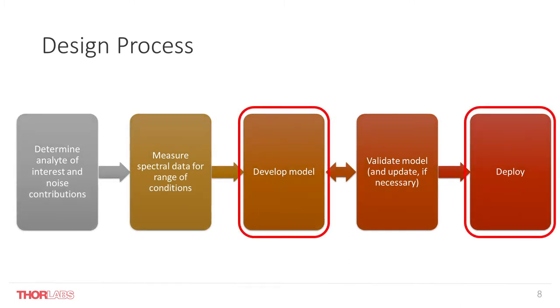Where MOEs primarily differ from a traditional spectrometer is in the model development and deployment phases. Our proprietary process creates a robust multivariate model from the spectral data. We then design a system around that model, which also dictates how much systematic noise can be tolerated in our final system build. When we arrive at a final model for our instrument, that model is encoded into our MOE, instead of being handled by post-processing.